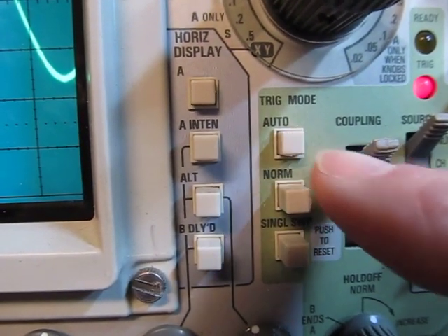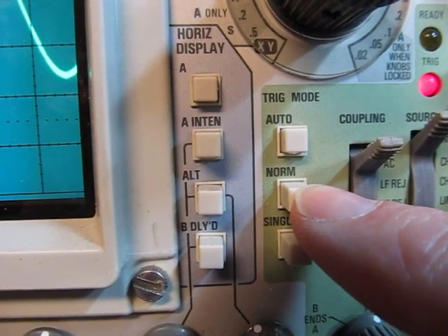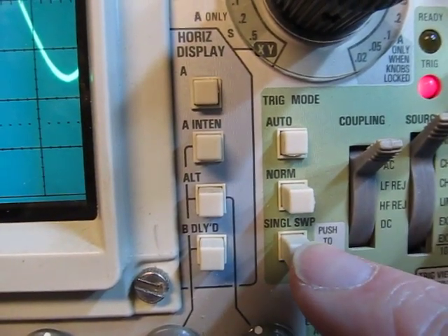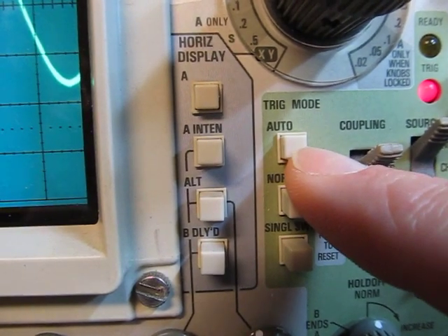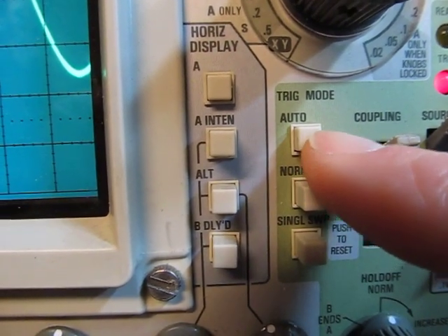We notice under the trigger mode we've got auto and norm or normal, and then single sweep, which is kind of self-explanatory. But I really wanted to talk about what auto-triggering means and what it doesn't mean.